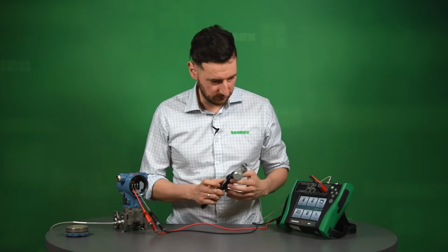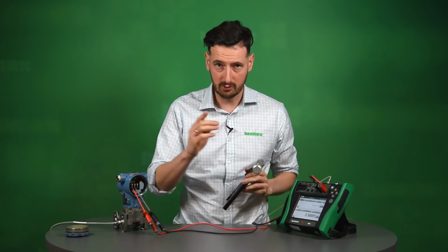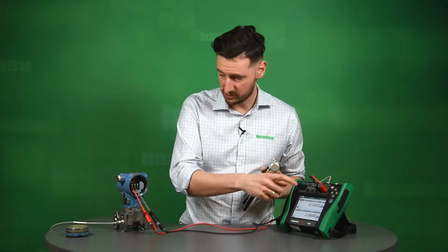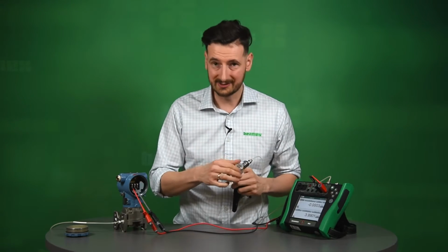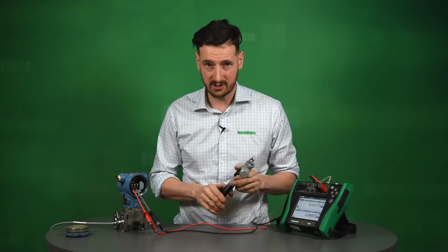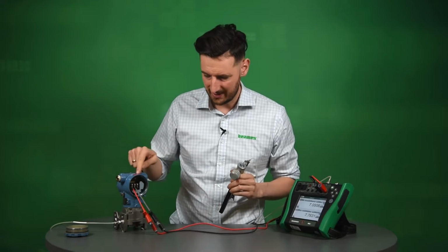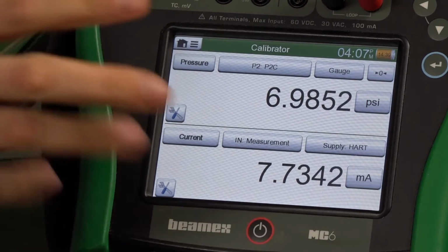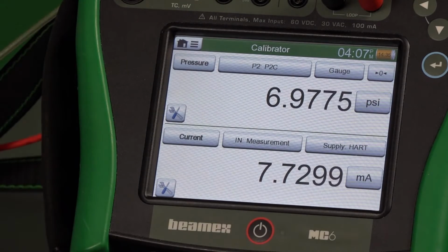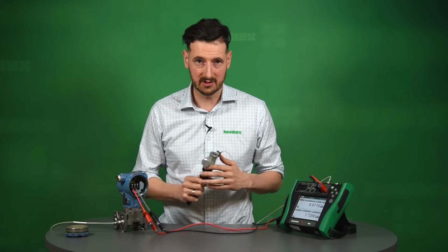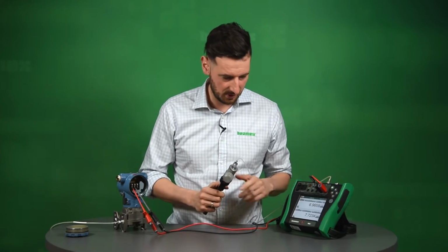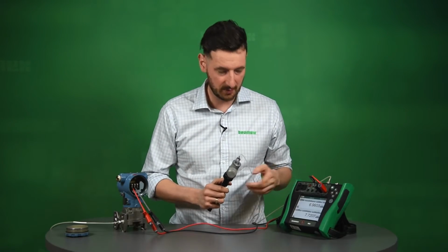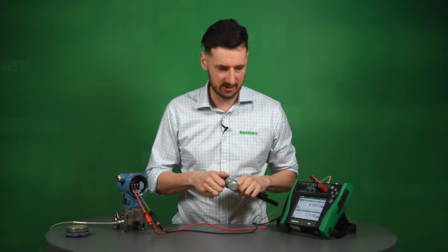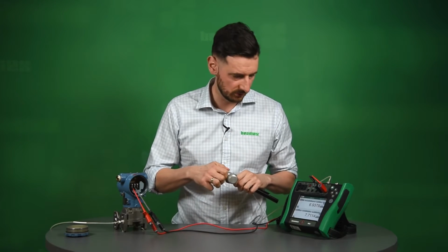The only thing to mention here is if we go to the calibrator and check our connections, we can test that very easily just by pressurizing the system and seeing if we have the milliamps response, a direct linear response from the transmitter. And it looks as if we've got a milliamps response directly to our applied pressure. So it looks like we're good to go.